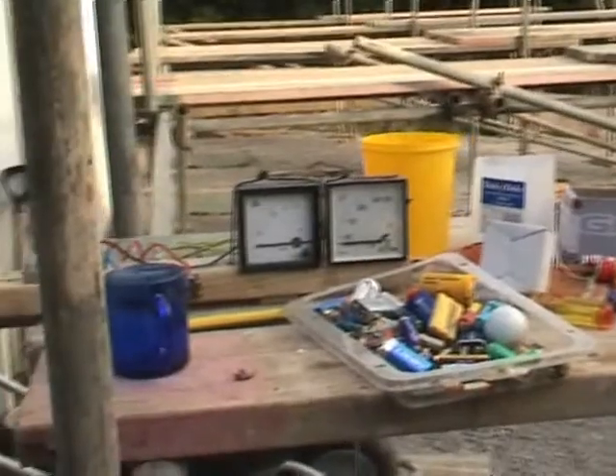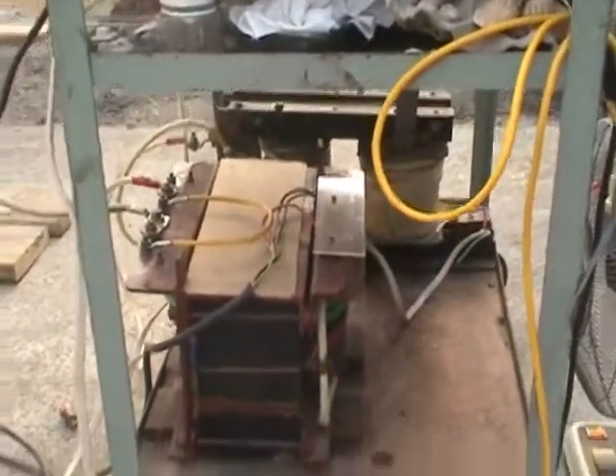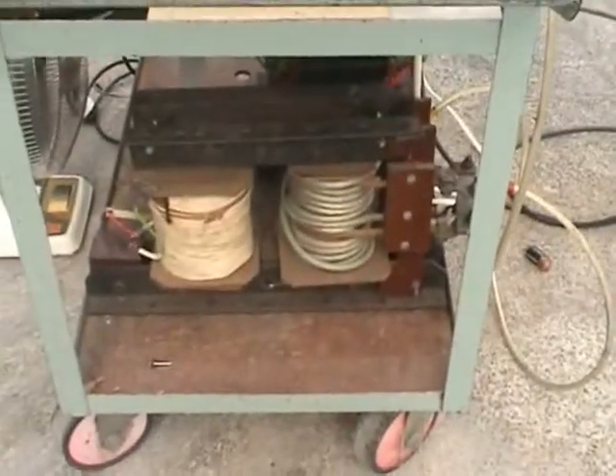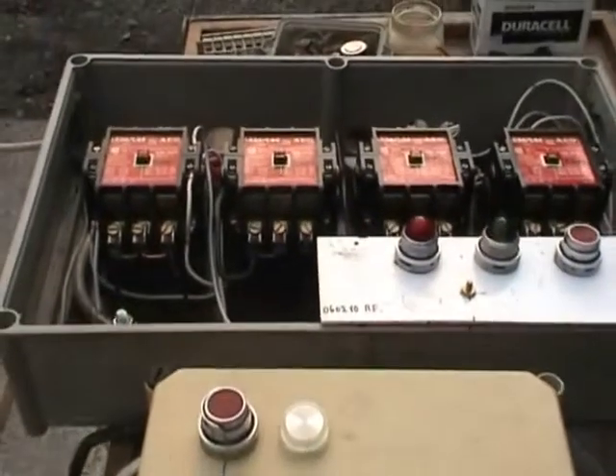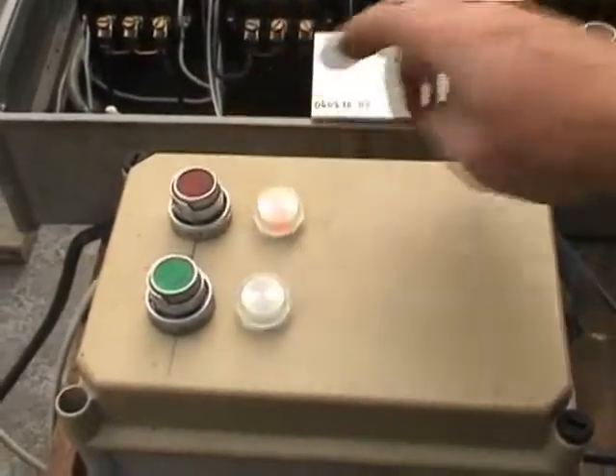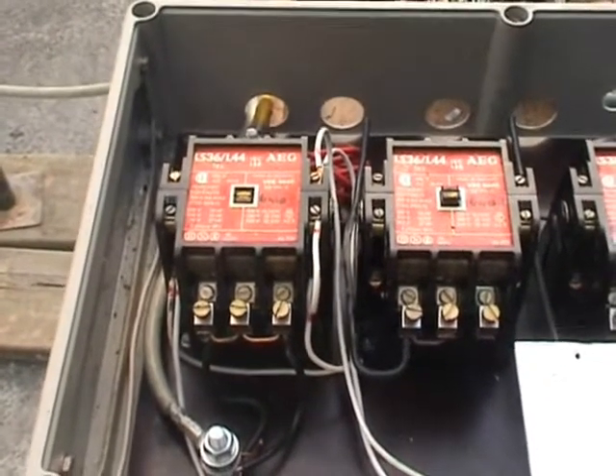I've got some spare batteries here and some other meters. And then I've got air cooling on transformer 1 and transformer 2 at the back. These are wired in series to give me about 40 volts AC at about 100 amps. These cables are going in series, just going up to the battery destruction area. I've set the control module up so I excite the transformer's primary excitation by pushing the button here. That gives 40 volts to the transformer, and the secondary circuit is switched by means of a big AEG contactor that closes the secondary contact.